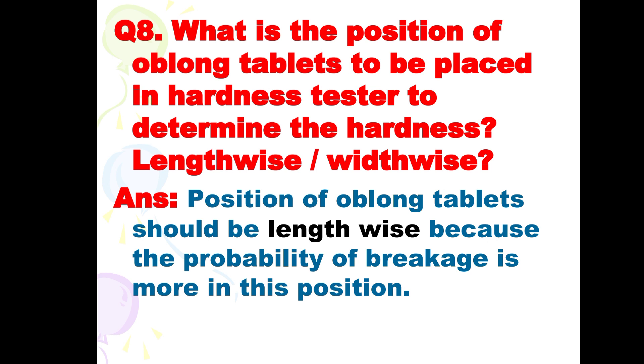Next is: what is the position of oblong tablets to be placed in a hardness tester to determine the hardness — lengthwise or widthwise? The answer is: the position of oblong tablets should be lengthwise, because the probability of breakage is more in this position.